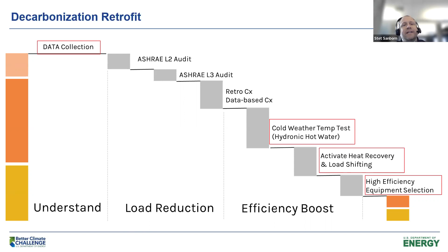As I mentioned, and as one of the Slido questions brought up, the supply water temperature we send from a heat pump, if it's an air-to-water heat pump, is really critical in helping us select equipment that's not only efficient but works in our climate zone. This building has typically been served by a 180-degree supply water temperature, which is excessively high for the Bay Area.